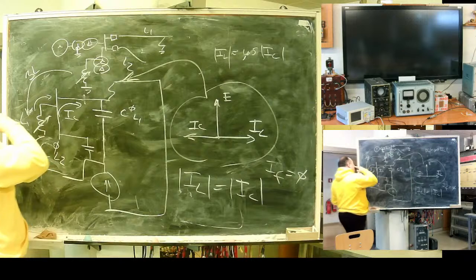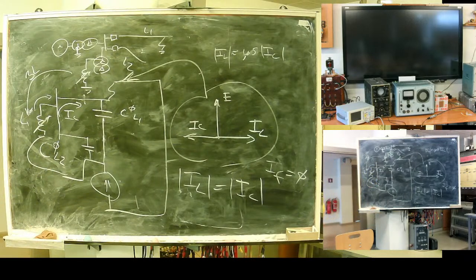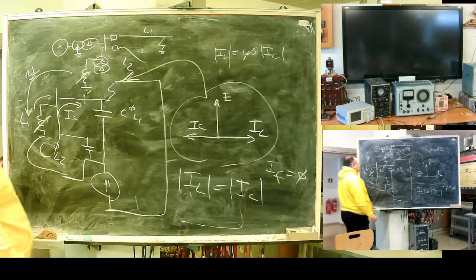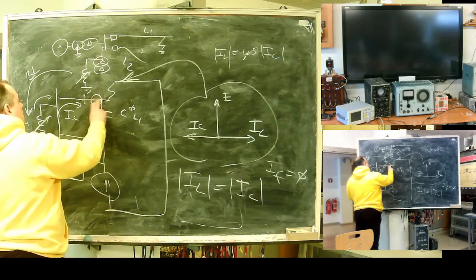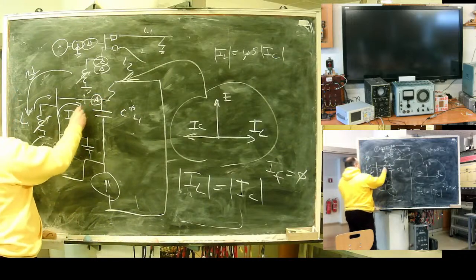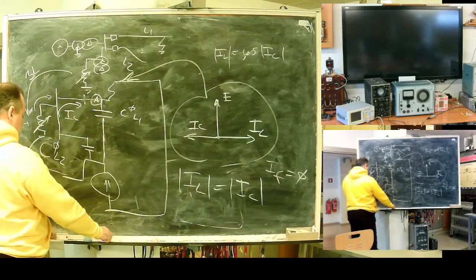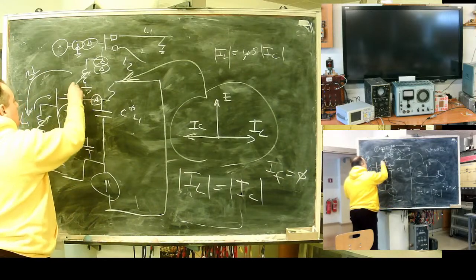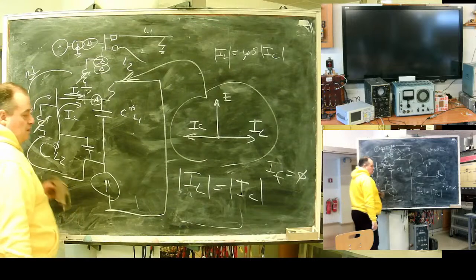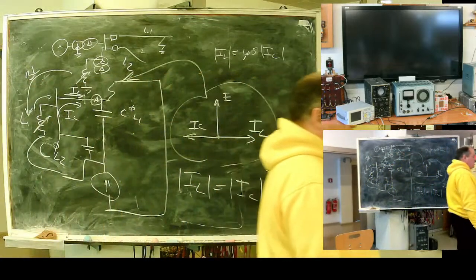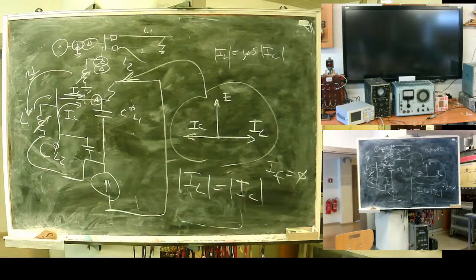Grounded neutral. What should I do? Here problem. My relay sits here, and it will see both current from capacitance and current from the coil. It's highly possible that current from my relay will be 0. It is very tricky moment. What to do?